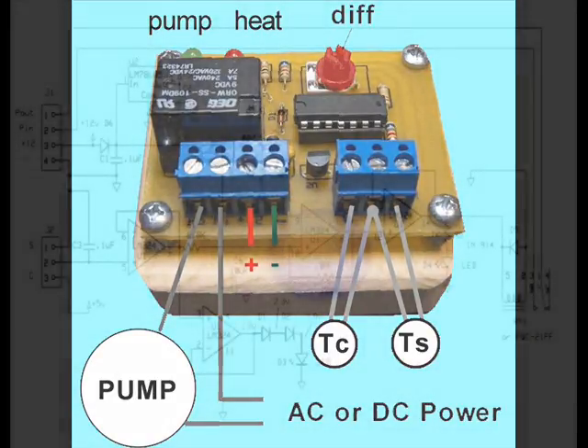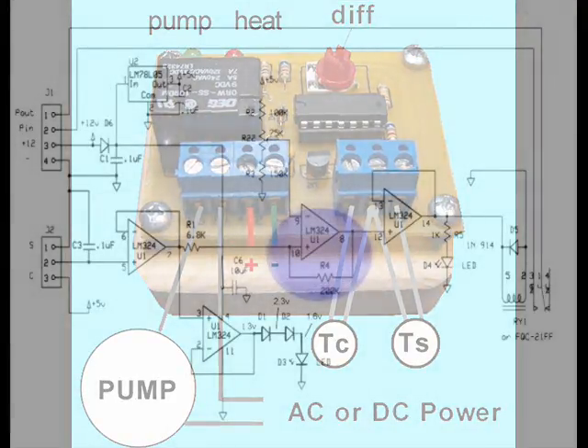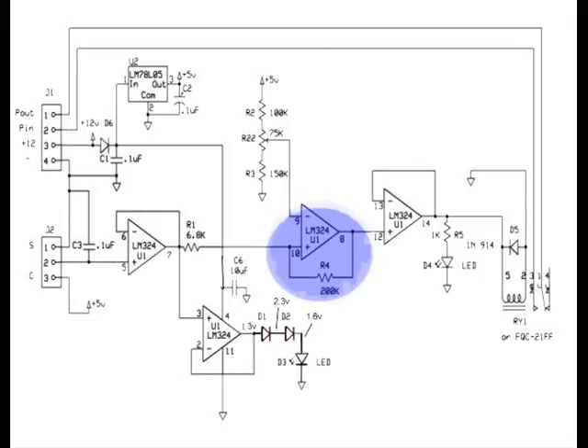Both adjustable thermostats and differential thermostats use a latch circuit to keep pumps on or off within a specified range. Without latches, relays would come on and off randomly and produce something known as chatter. Chatter puts undue stress on relay contacts and decreases their life expectancy.